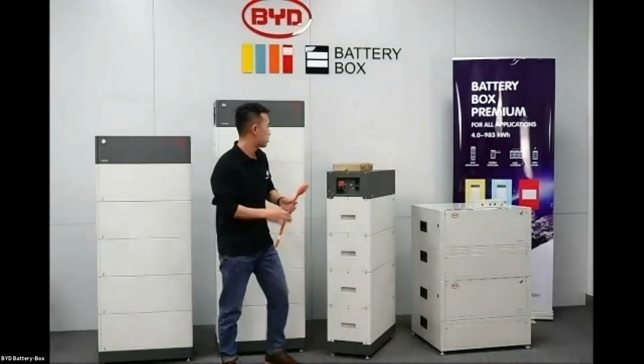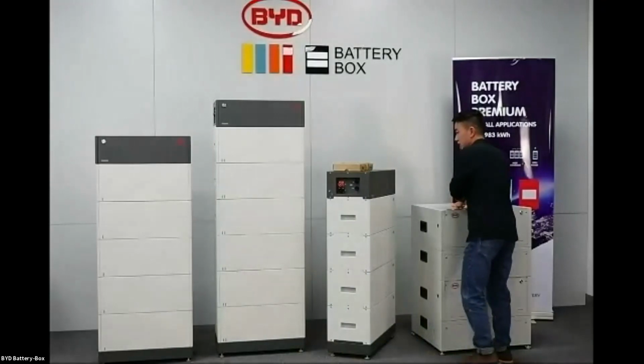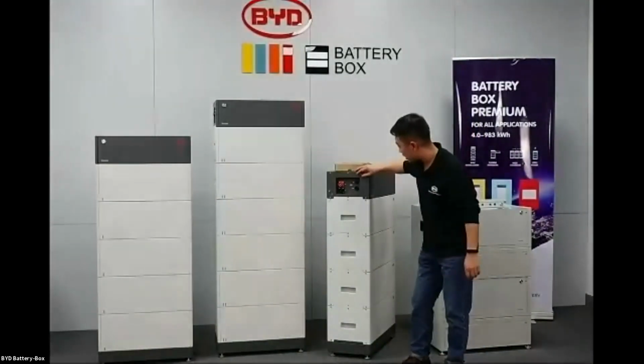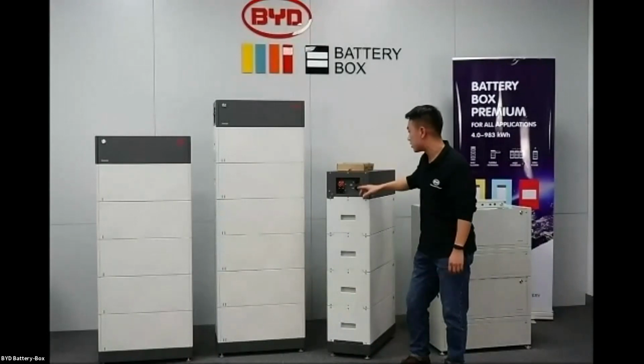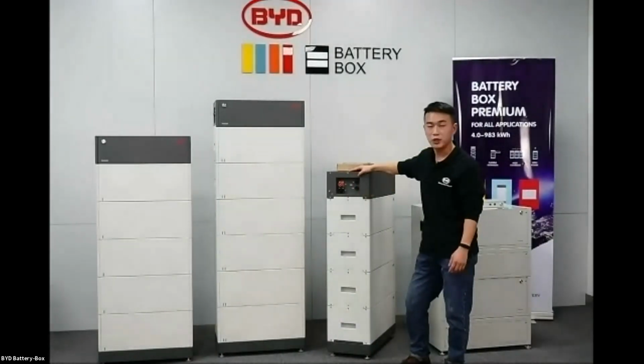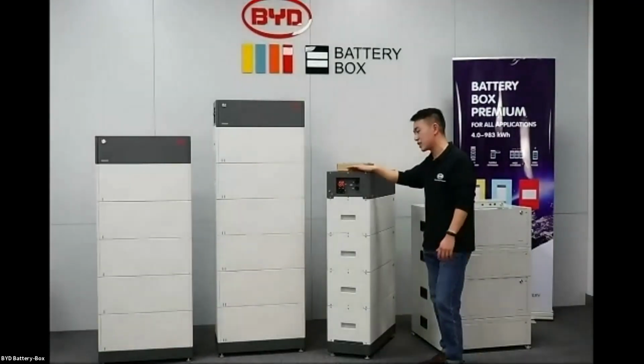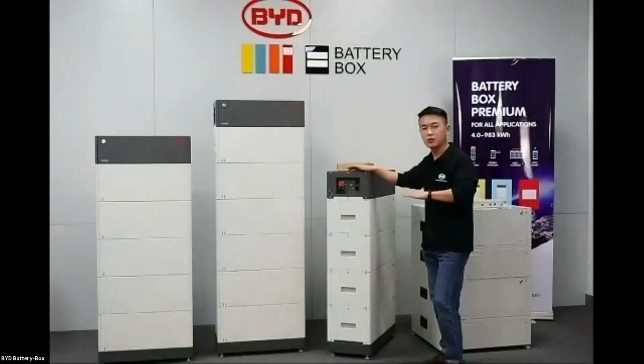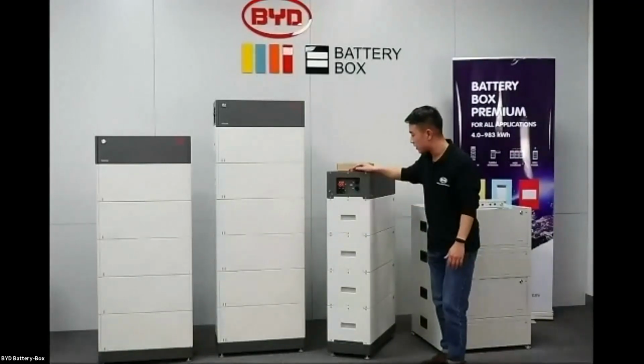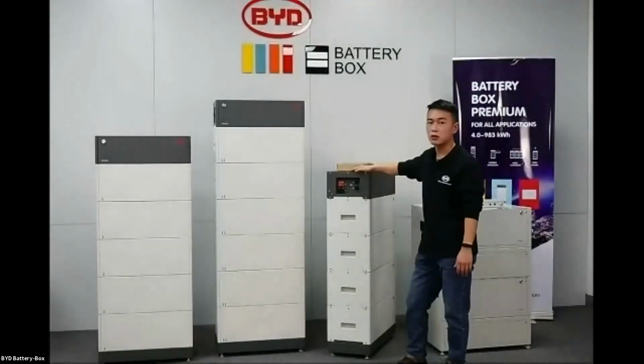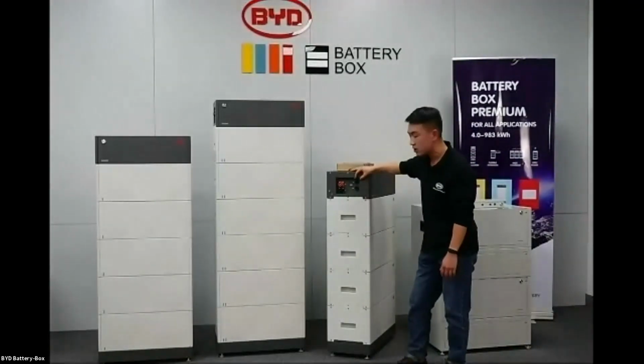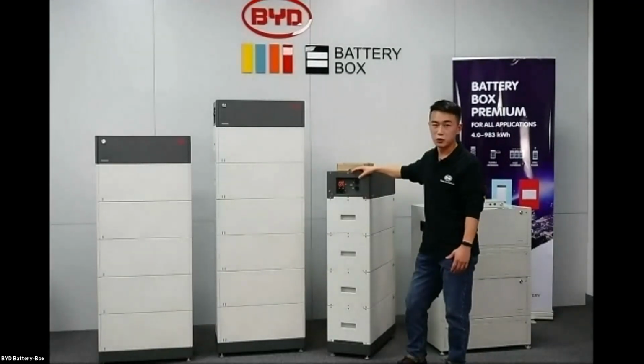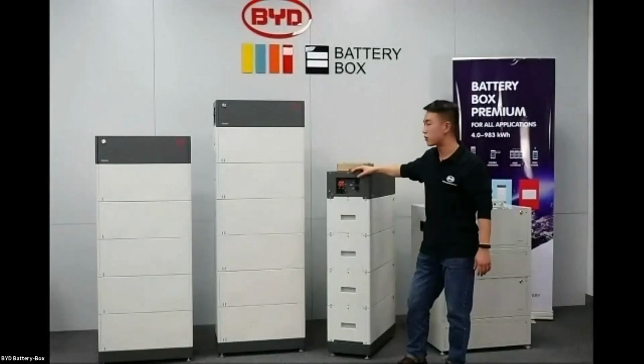The two ports for communication connection on the upper side also play the parallel connection function. Please follow the manual. The LVS is capable of stacking in parallel up to 64 battery modules, so you can get a very high capacity. On the very first tower, the first port is for communication to the BMU and then to the inverter side.